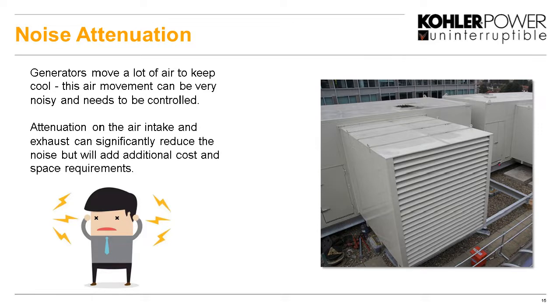Engines are noisy. Actual movement of air is also noisy. And we have to move a lot of air to keep this generator cool. Okay, we've seen the big radiators on there. So depending on the environment where the generator is located, and the regulations around it, we have to make sure that the engine is running to those requirements. And that might mean putting some large noise attenuation on. Now, these can actually take up significant space, but they do reduce the noise, and sometimes it's essential. But these will add, obviously, cost and space requirements onto that generator itself.